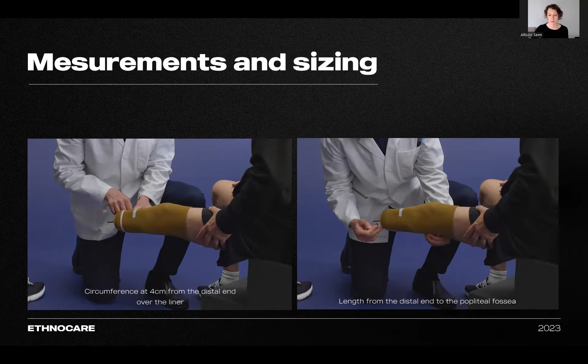So to find the correct size of the Ethnocare overlay, 2 measurements are needed. You're first going to measure the circumference of the limb at 4 centimeters from the distal end over their liner to determine the width. And then the second measurement is the length of the residual limb from the distal end to the popliteal fossa to determine the overall length.